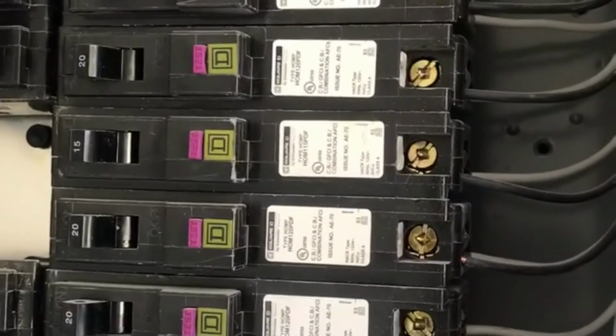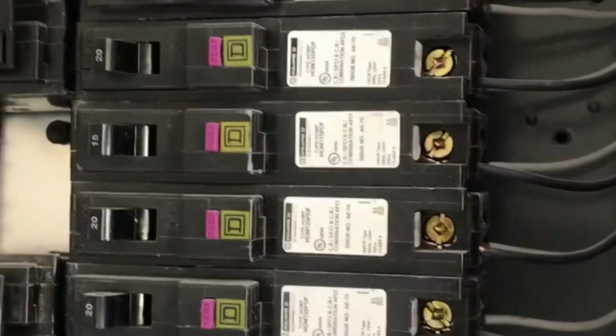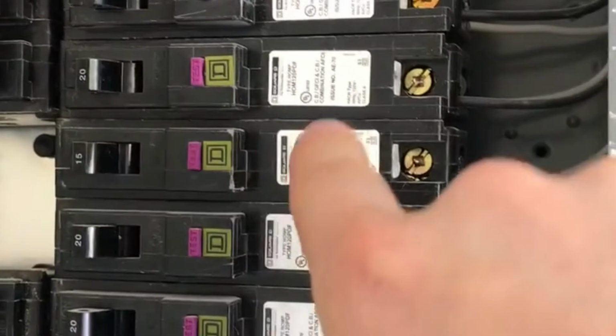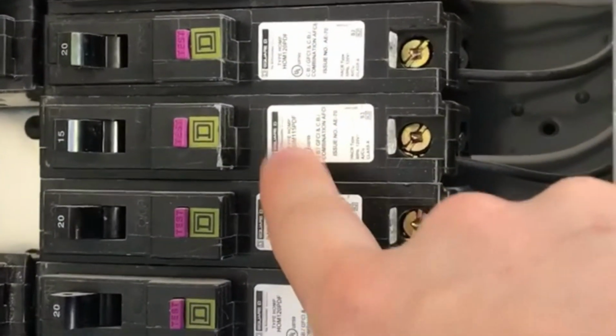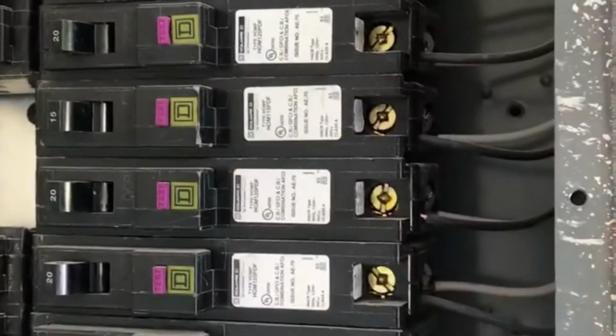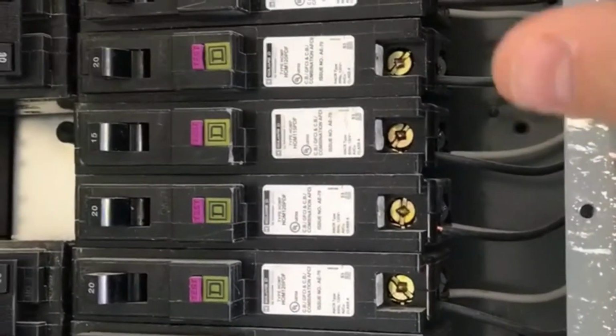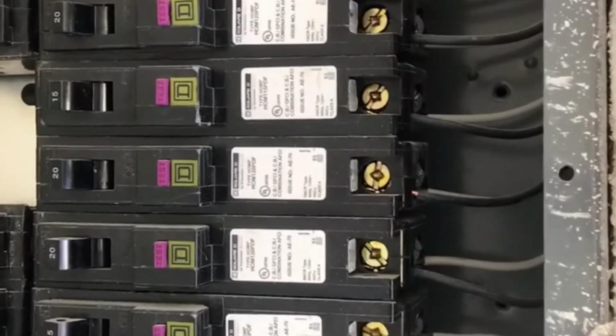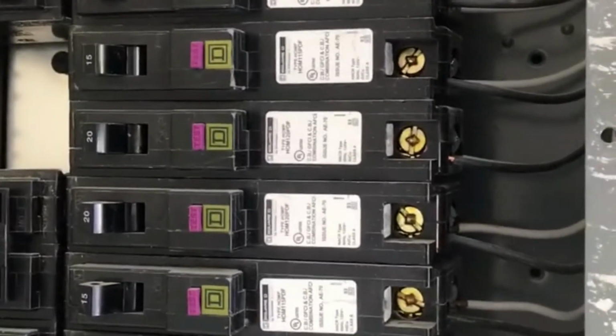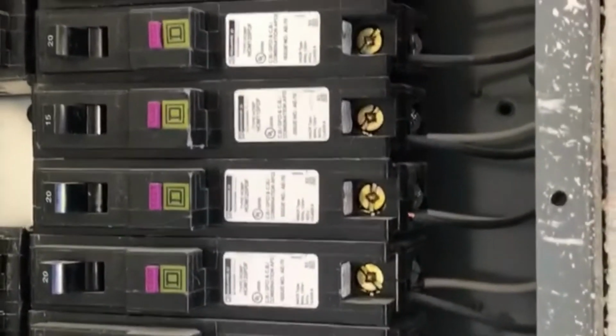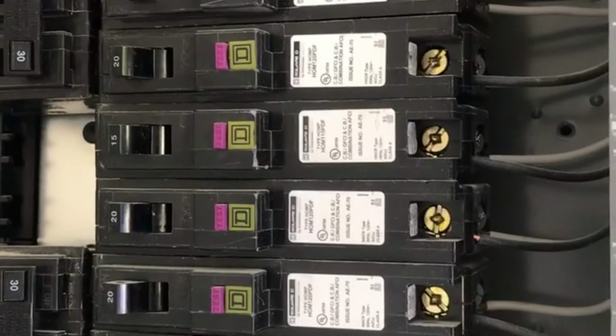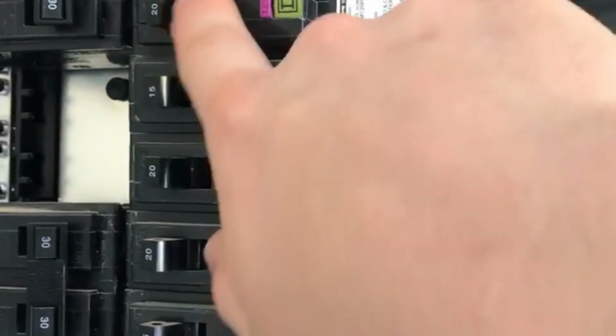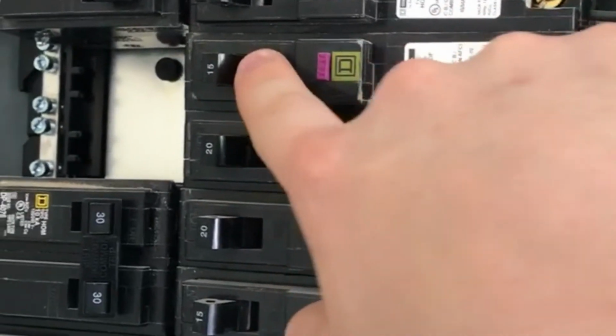Also, when deciding whether to use a 20 or 15 amp breaker for a 120 volt circuit, you need to decide what the circuit is dedicated to. For example, code in Kentucky requires the refrigerator and the microwave, the disposal and the dishwasher all to be on separate breakers. Depending on the requirement for these units is what would decide how many amps each circuit needs to have.